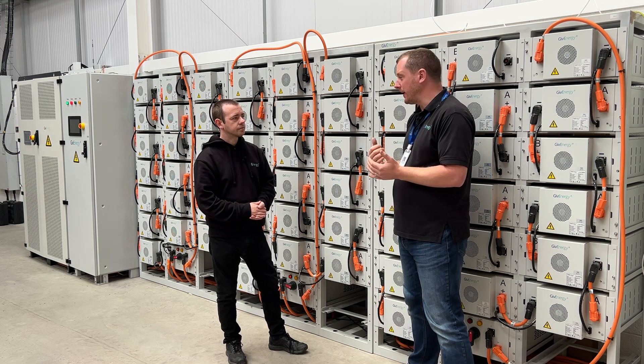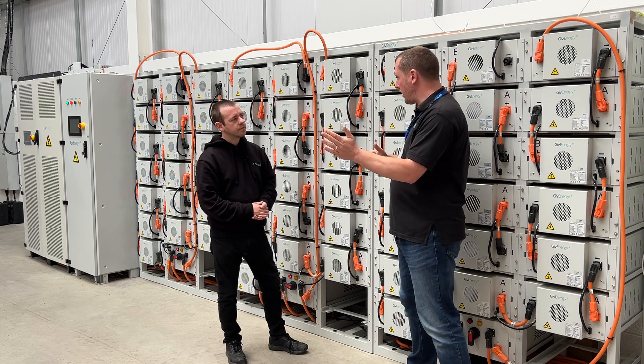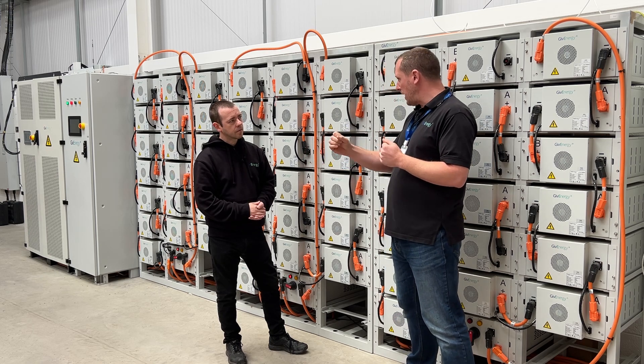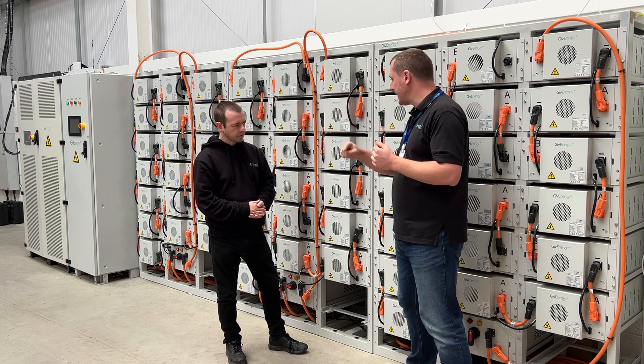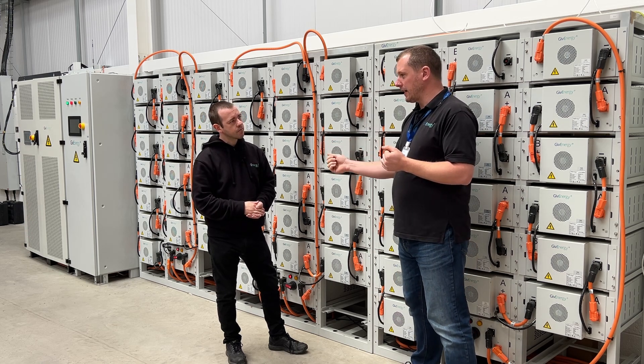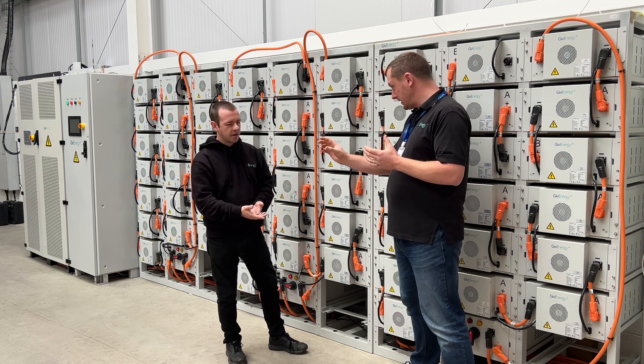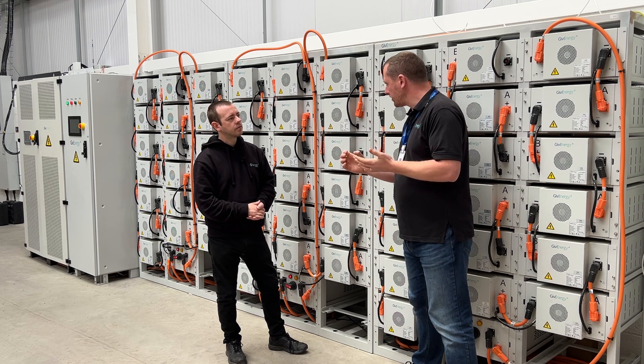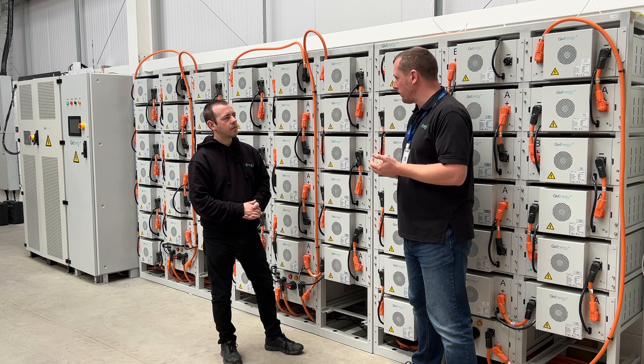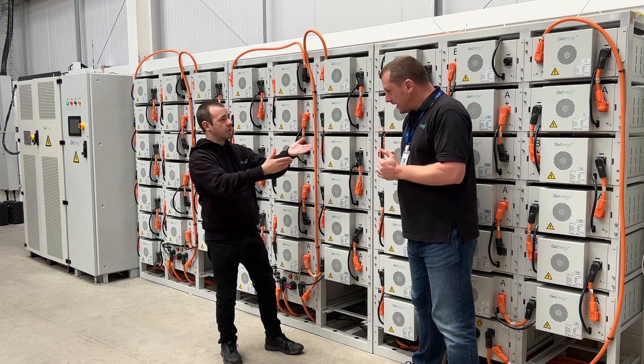One example of that is peak shaving. If you have a factory that runs between nine and five on weekdays, you have pieces of equipment that take a lot of power but for a relatively short period — think of something like a heating furnace, a big peak. You have to pay your electricity supplier commercially to have that amount of power available. You pay for what you take, but you also pay an availability allowance. So if you need one megawatt of power at any instant, you will pay for 1,000 kilowatts of availability even if your usage throughout the whole day only sums up to five minutes.